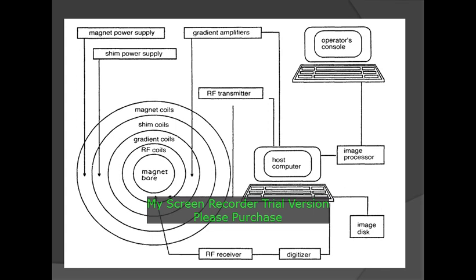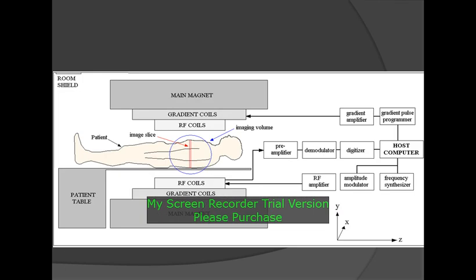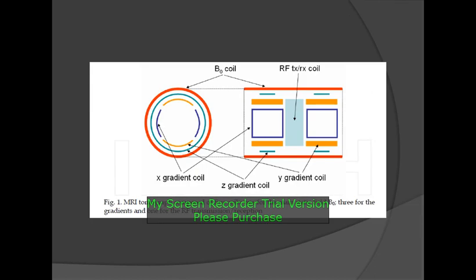This is the schematic diagram of the coils. Inside the magnet, there are gradient coils, and inside the gradient coils, there are again the RF coils. These are the RF coils, X gradient coil, Z gradient coil, and Y gradient coil. The MR tomograph is composed of five coils.